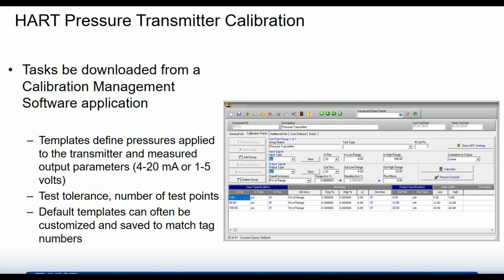So let's take a look at some of the benefits of having that software. Okay, for one, once you have your instruments loaded into your software, now you can select which task you want the technician to perform. So let's say you want technician Bob to go out to a boiler and calibrate 5 transmitters out there. Well, you can select those transmitters and download that information. And all that information is built in to the task. So those templates can be downloaded quickly to the calibrator, and then once those calibration results are done, you can upload those test results and they'll get populated into the database, easily accessed by whoever's using the software.